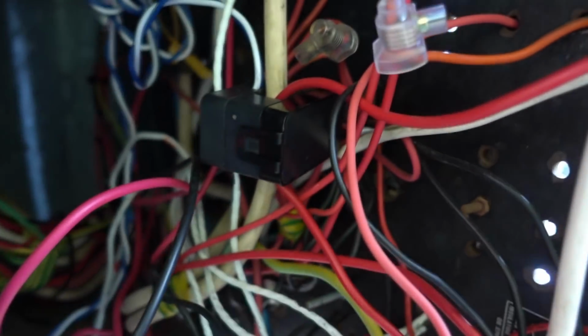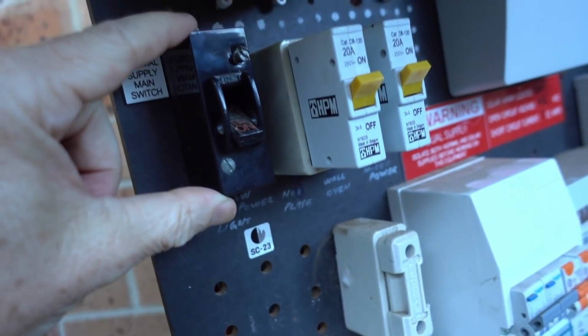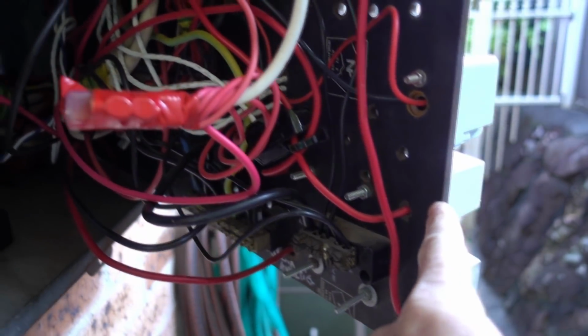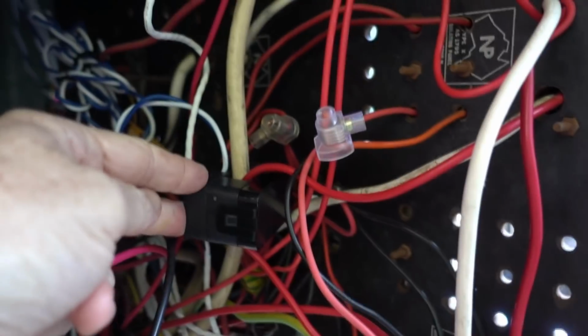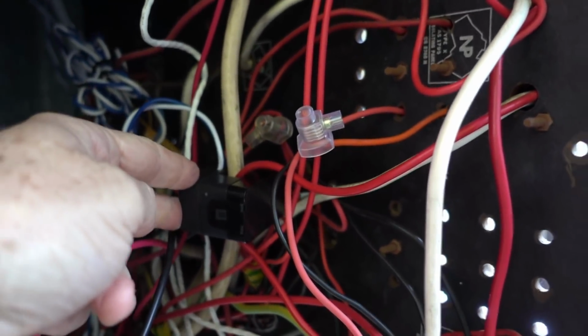So it depends on the orientation of that wire, whether the current's flowing that way or that way, whether or not it subtracts from it. But I didn't have to touch the wiring, I just had enough lead length going from here up there, well, through the transformer there, and over to the main. This is the main breaker for the whole house. So the 3 kilowatt production runs through the transformer that measures the consumption. So if you put it through the opposite direction, it will subtract it out, and it all comes out in the maths in the end. So yeah, that's the only change.